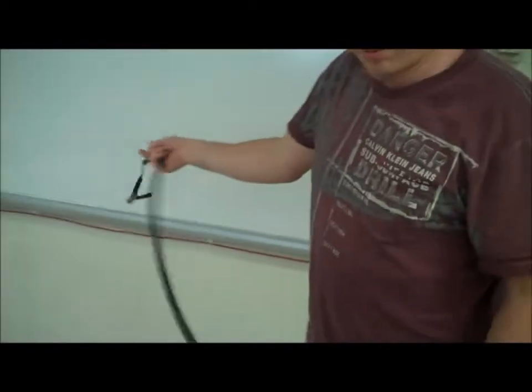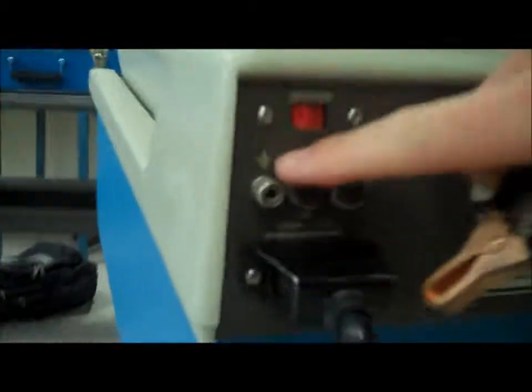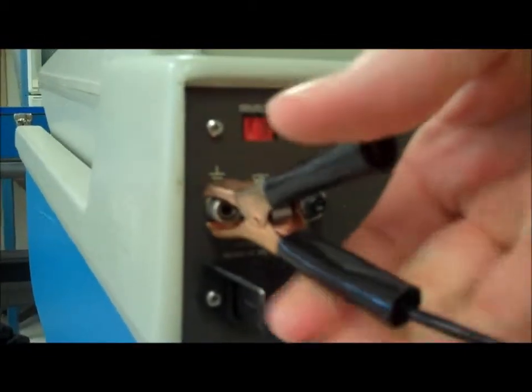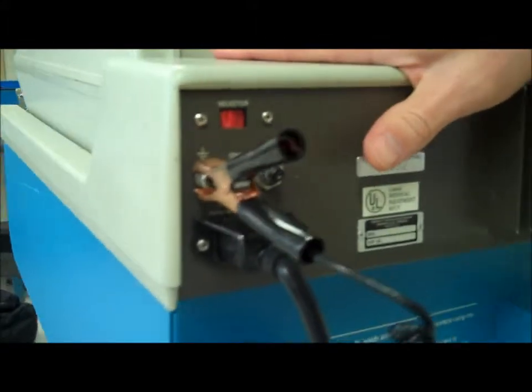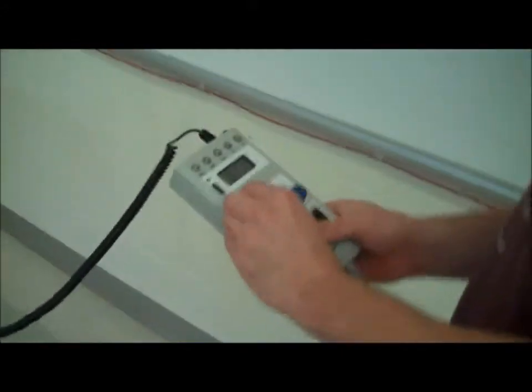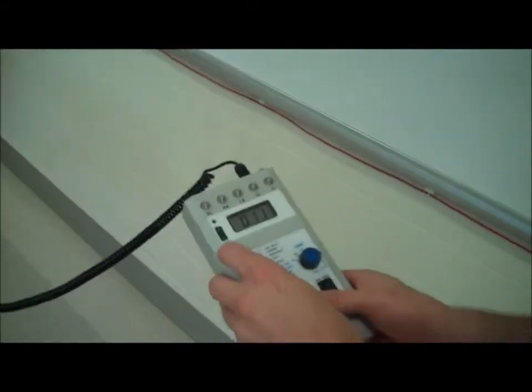And I now need to plug in the Kelvin cable of the electrical safety analyzer to the back of the defibrillator, which you'll notice the ground symbol here. This is to do an electrical safety check for chassis leakage. But first thing we want to do is verify the line voltage going in.